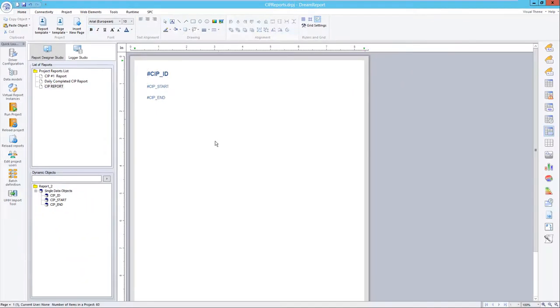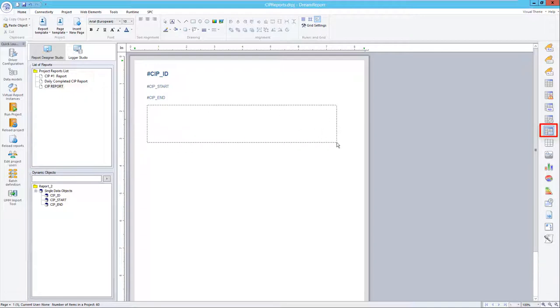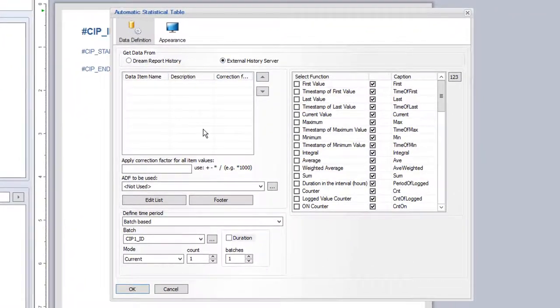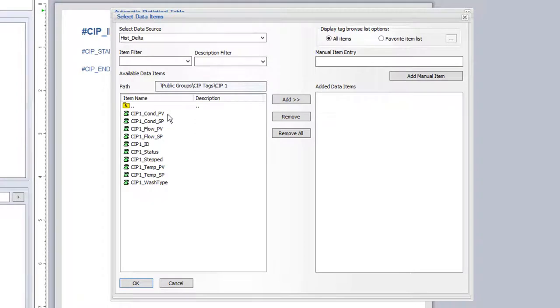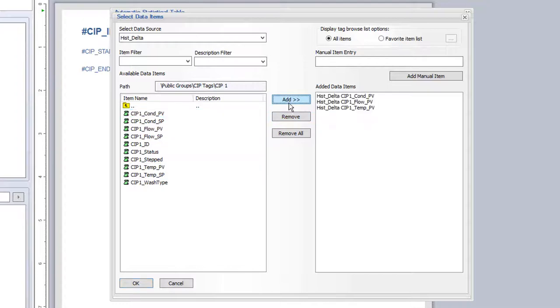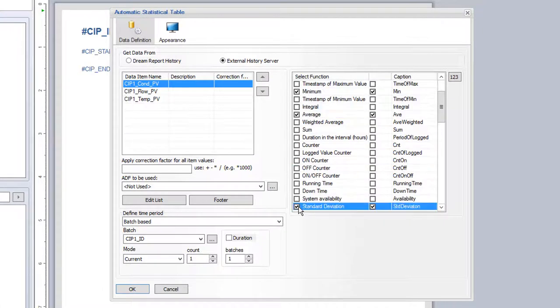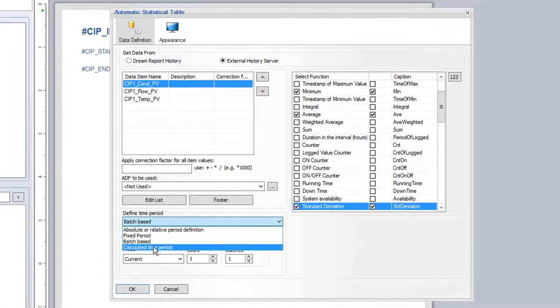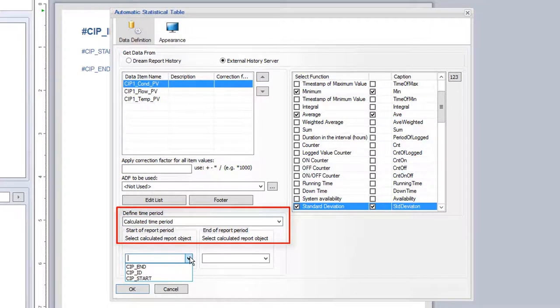Once these two objects are defined with our CIP start and end times, we can then place any objects we need on the report, referencing the start and end time objects for the time period to use. Let me start with the automatic statistical table to summarize my PV tags for the CIP report. I'll browse for those tags in my historian, pick the temperature, conductivity, and flow tags, and once I've selected those and assigned the statistical calculations, I'll use the calculated time period pointing to my start and end objects on the report.